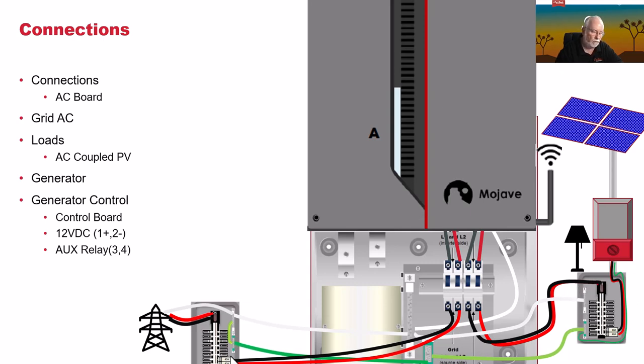Power, same thing, comes off of a backfed breaker. We have our line 1 and line 2, which again will carry up into the inverter. They come out of the inverter on the other side through the AC board, and then these two outputs go to the input of the backup loads panel. Our grid direct PV then attaches. Our grounds are carried through the whole system.